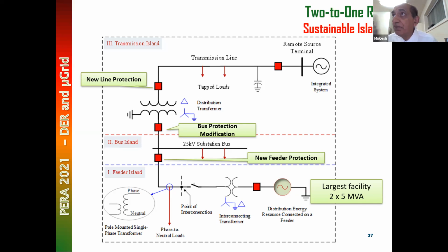But I think there's an important question. The important question is tap changers, the voltage regulators. They have to be programmed for reverse power flow. They have to be reprogrammed. They have to be programmed for bidirectional flow, so that voltage control is programmed for bidirectional power. That causes tap changers to cause a problem, not the transformer.